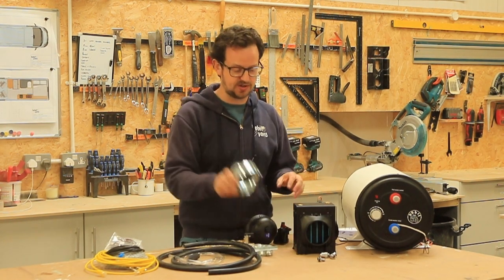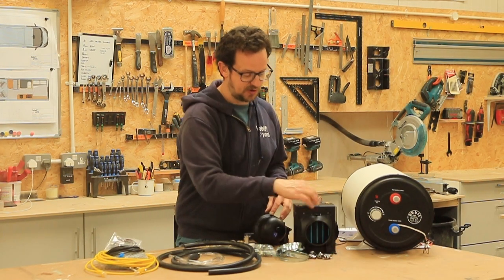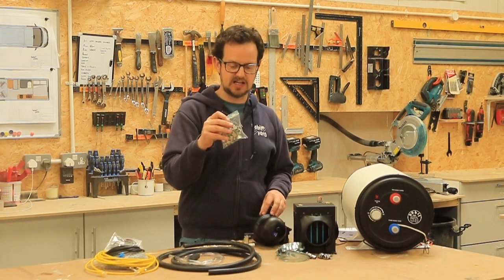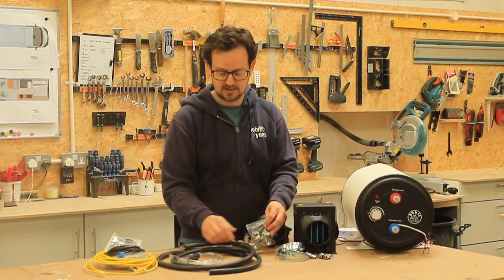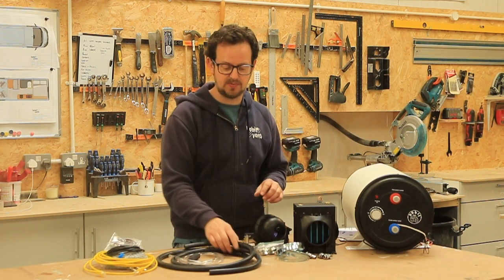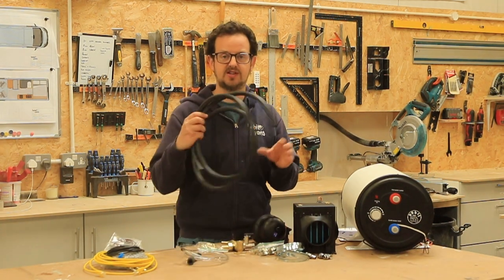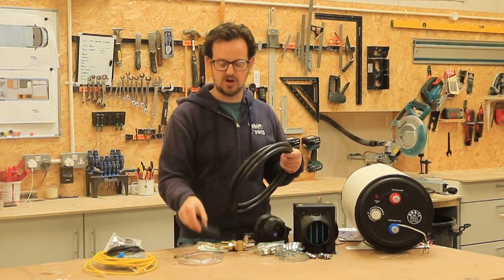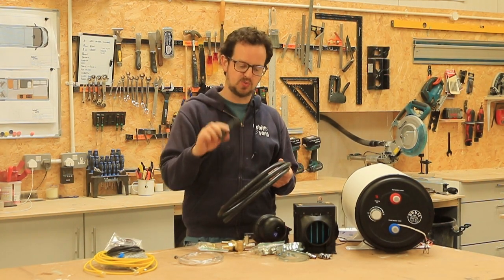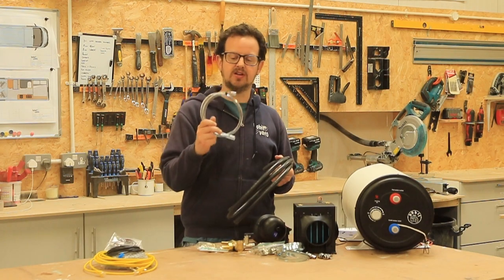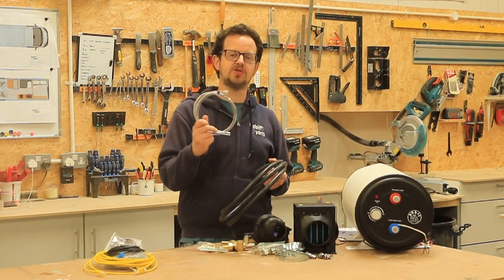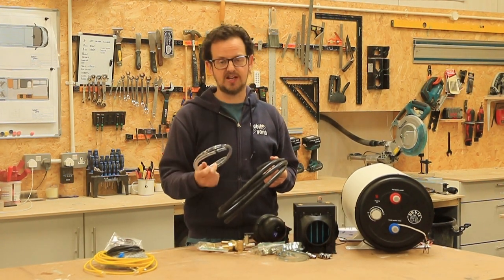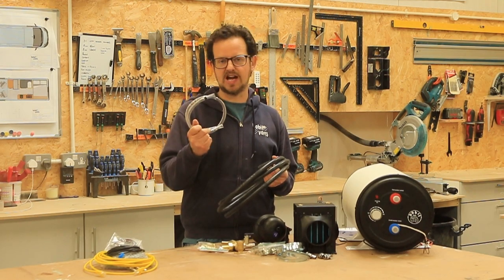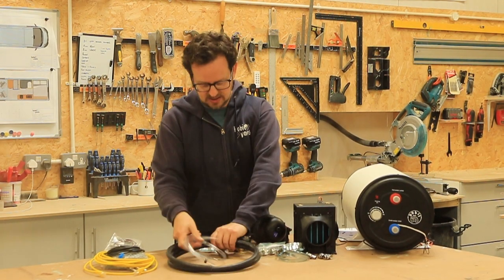Large Jubilee clips for your ducting, fittings for your heat exchanger, small Jubilee clips for the hose, which comes in 3 different types. You've got 10mm hose, which is most of the system. You've got a little bit of 13mm hose, which is for the pump. Then there's a section clear. This goes on the overpressure valve, so if you want to drain it, you just drain it out through this hose out of the van.